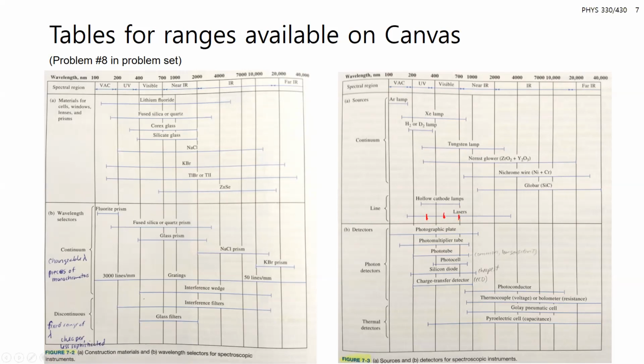So when you're using an instrument, you should look in the manual, of course, at what wavelengths it works for, but also at what lamps it's using in those different ranges, or what detectors, if it's using multiple detectors. Let's say you want to measure something in the mid IR all the way to the visible, you might switch between detectors as well, and that can have different calibrations and different sensitivities in those ranges.